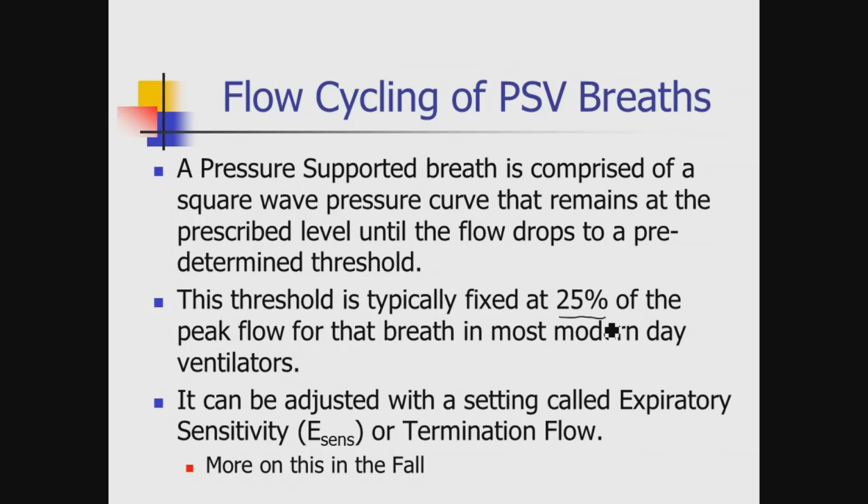You betcha. Typically 25%. So when this thing turns on, here's my square wave pressure curve, and here's my flow rate. If this is 60 liters per minute, when the valve opens, flow comes out at 60 liters per minute, totally dependent upon the patient. It's whatever they want to draw.